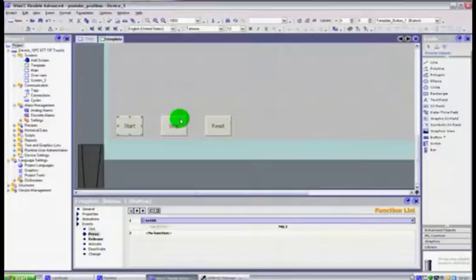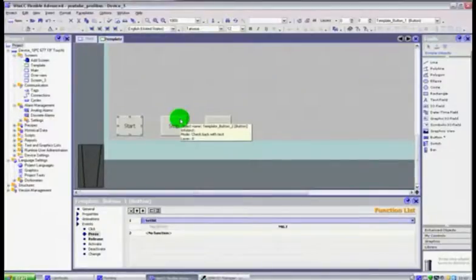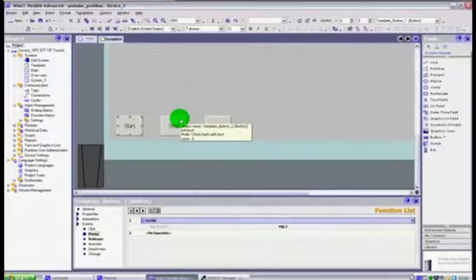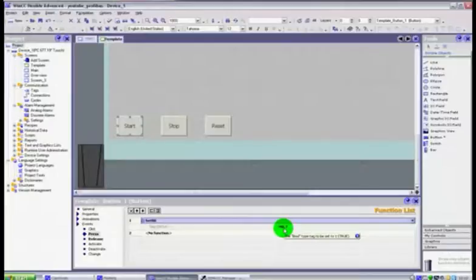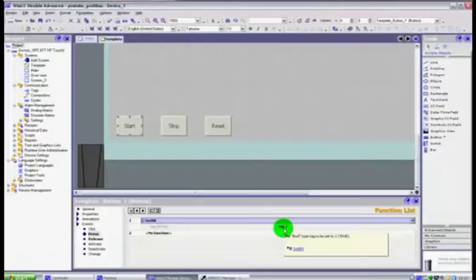You will now see that you've got a press state of set bit and a release state of reset bit and it's the same bit. So now when I press that button when we're in run mode with the HMI, whenever I press that start button it will set M0.7 for me and when I take my finger off the button it will reset it. And it will inform the PLC of that because of the connection.